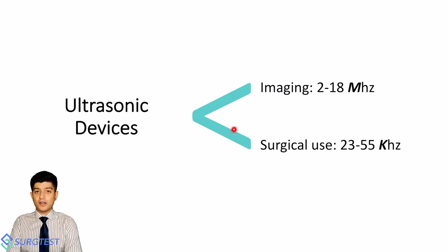And essentially, it's happening at this working end of the ultrasonic energy device. There is back and forth movement. Electrical energy is converted by means of a piezoelectric crystal into this to and fro oscillatory movement that happens at the business end of the instrument. Note that only one jaw of ultrasonic devices is always going to be articulating. So you only have a single action jaw.